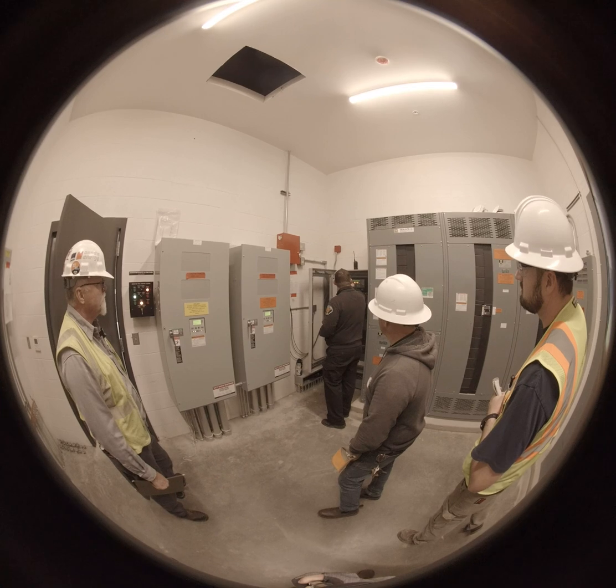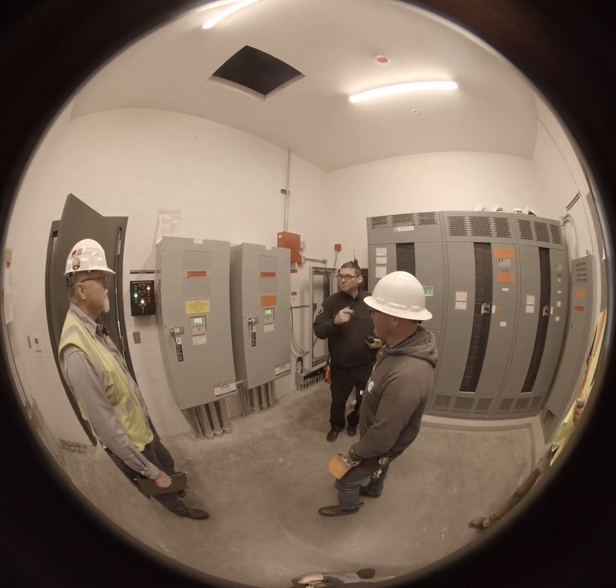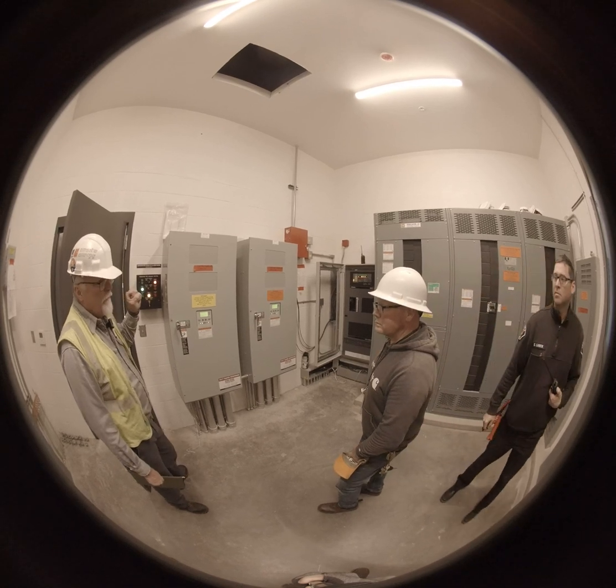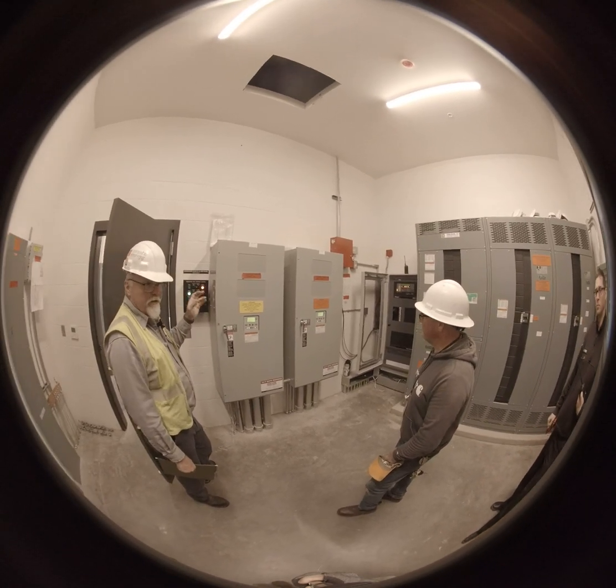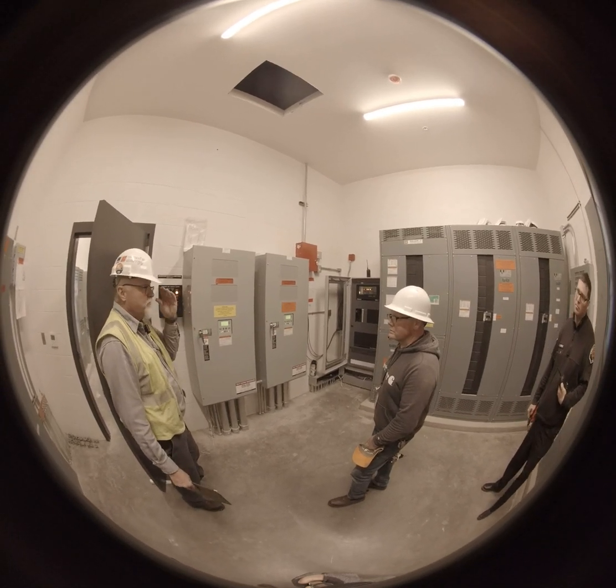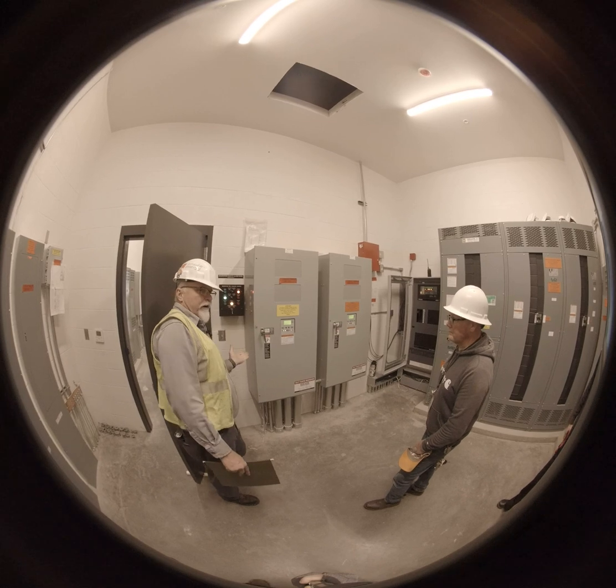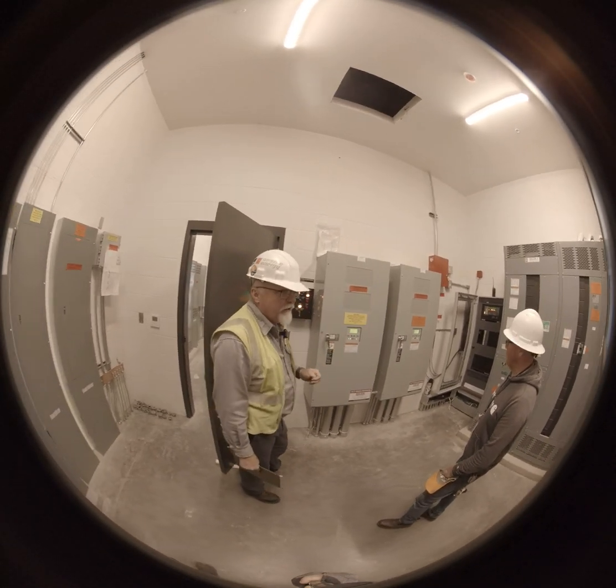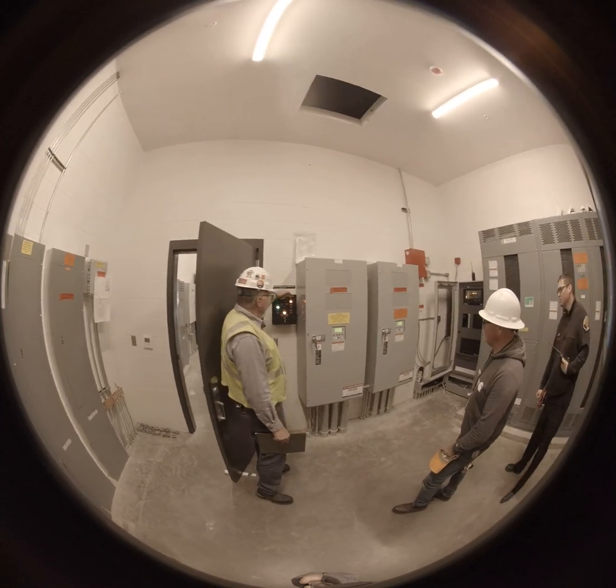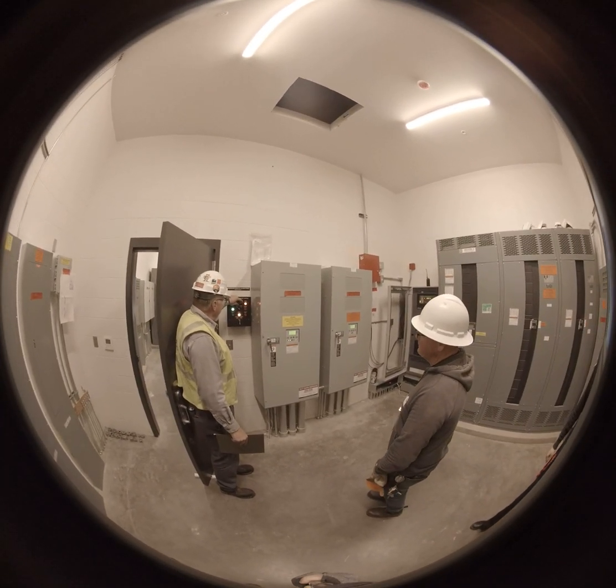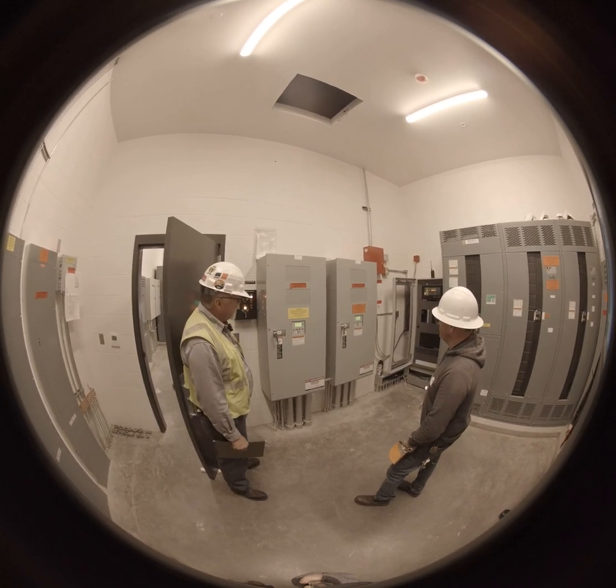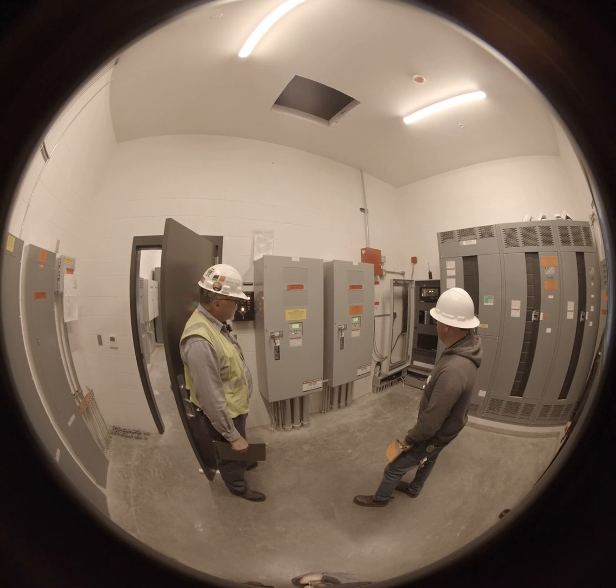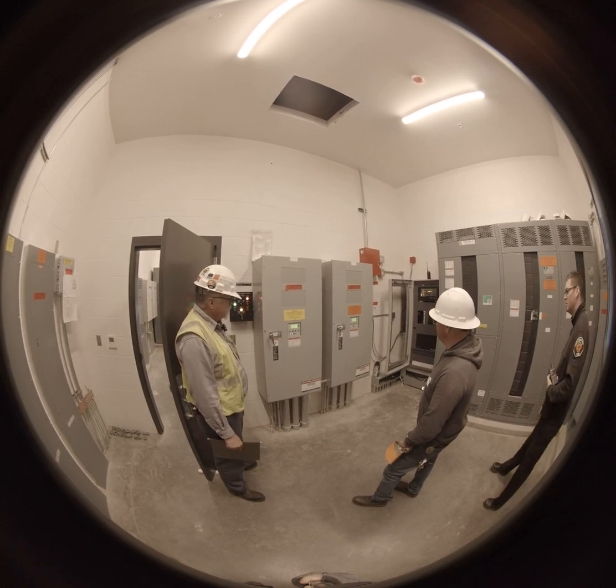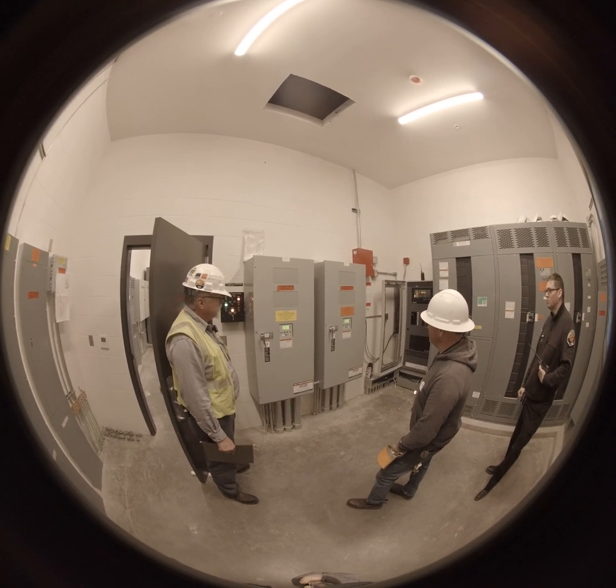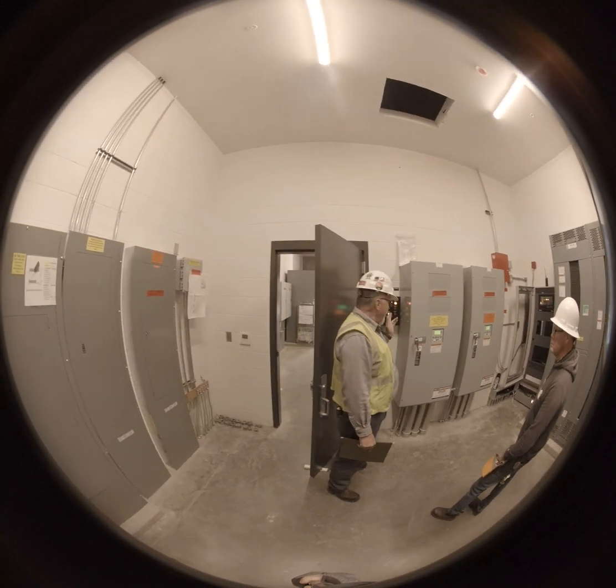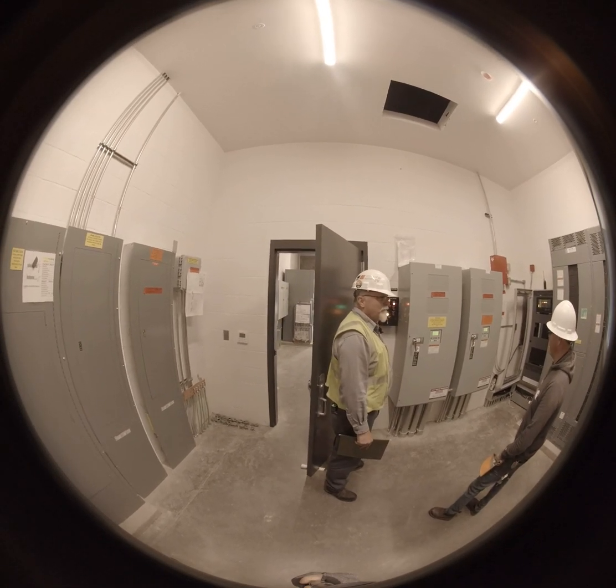And we got a trouble, FACP, AC failure. Now, I have these set up for 30 seconds for test mode, because this here is not an actual outage, it's a forced outage. So when I turn this back, you will see this display come up and it will start timing out. Of course, you see the red light here and everything switched over like it's supposed to. So go back over here. We should see timing. And if you would have been counting, from the time I flipped that switch until it switched, pretty much what our...